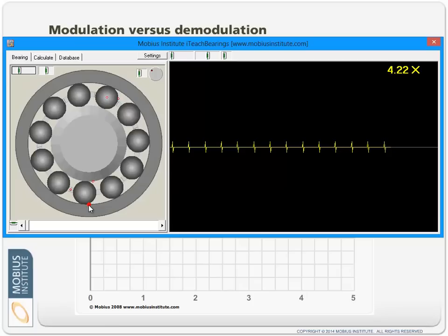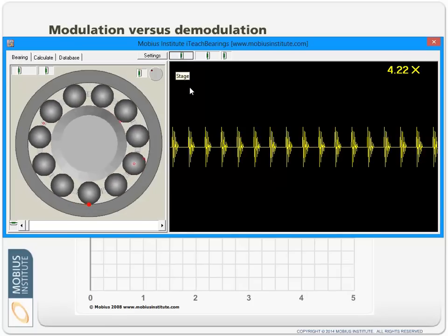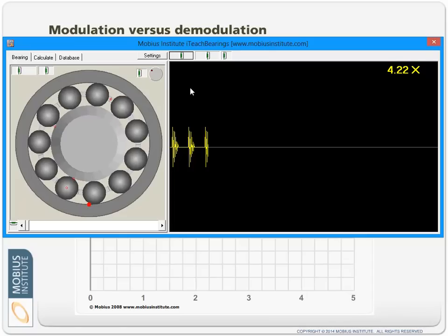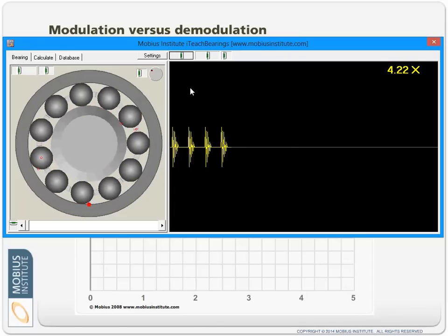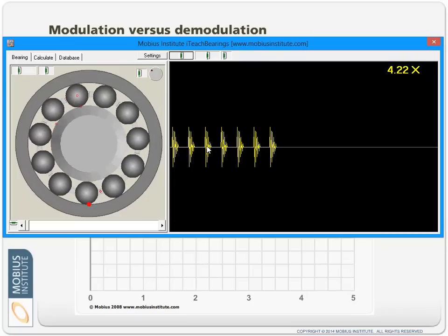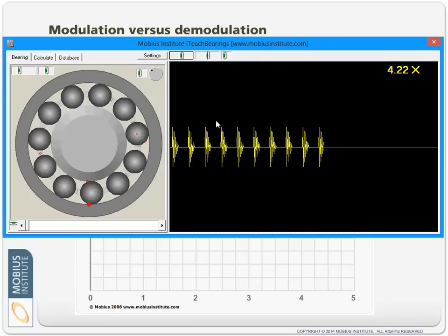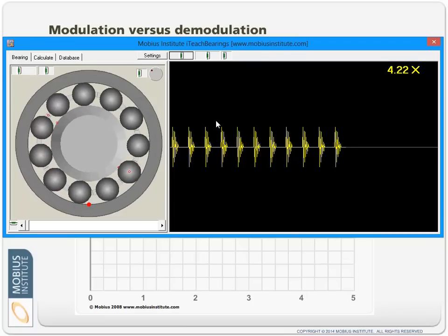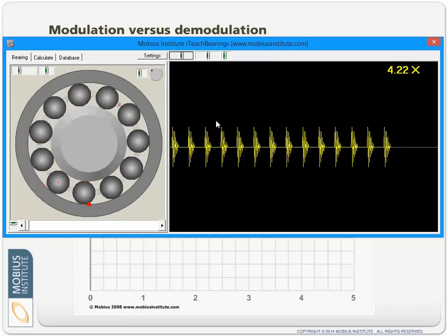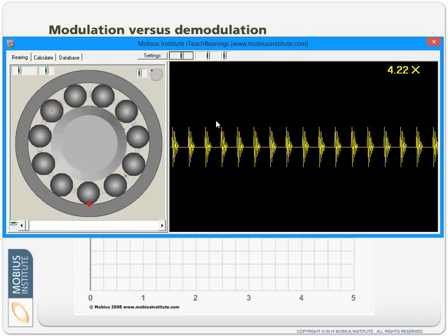And so what we've been left with now is just this waveform. Now what I'm going to do is just increase the amplitude of it so it's a bit easier to see. I've just got ring, ring, ring. Now this is all a higher frequency source of vibration. What we want to do is make it easier to capture this, because the stress wave or shock wave or the ring could be very short in duration, harder to detect. So we go through an enveloping process or a demodulation process. It's actually the same sort of process that they use in AM radios to extract the sound of the DJ on the radio from the carrier frequency that was used to get it to your radio.